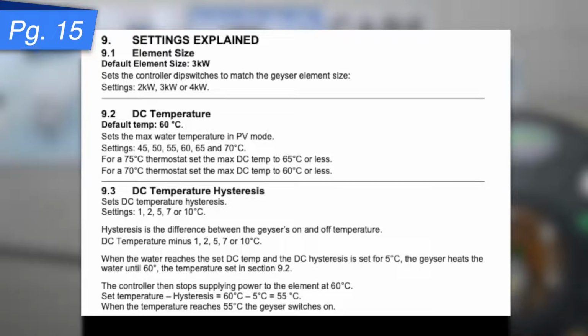If you have the Wi-Fi module, which Pierre will chat through a bit later, then you will need to use the Wi-Fi module to make the change. But if you don't have it, you're going to need to use the dip switches inside the controller. So right now you are set up factory standard for a 3 kilowatt element. The default temperature on the DC temperature side is 60 degrees. Again, if you want to change that, you're going to need to do so with the dip switches.